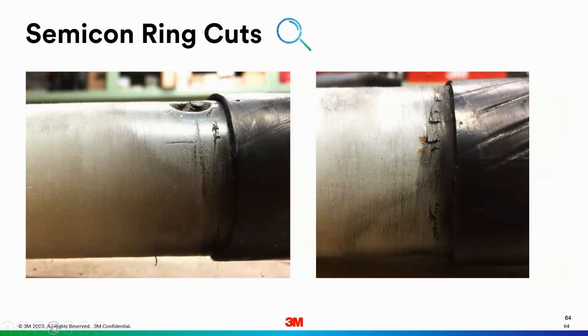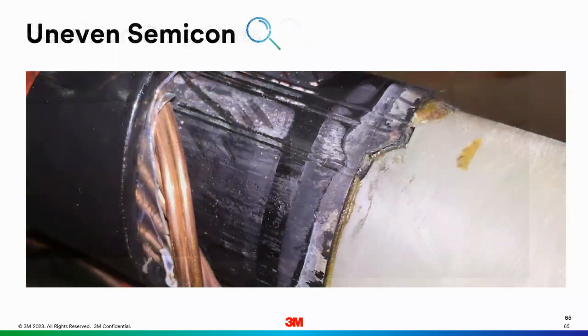Here's a big one. So this is the semicon cut. The black is the semicon layer. The white is the insulation, and you see those cuts in the insulation right above the semicon. That's going to lead to a failure every single time. You'll see that hole in there. It's caused by what is called the corona effect, and that's why you can't have any imperfections in this insulation, because it'll just drill a hole right through your cable, right through your accessory. This is very bad here.